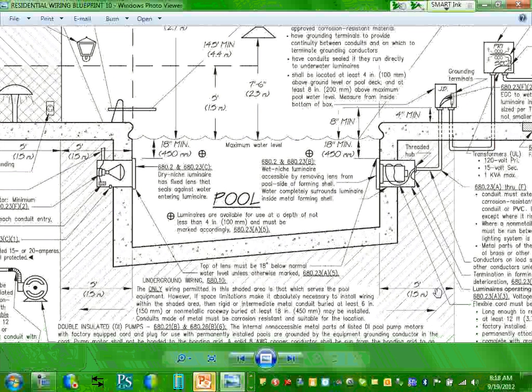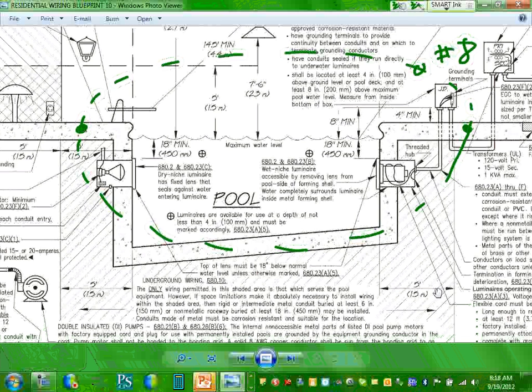All this, guys, is bonded together. What they do is they also put a number 8 conductor around the whole swimming pool. This is number 8. So as you walk the perimeter of the swimming pool, guys, I'm walking on grounded concrete, or it doesn't have to be concrete, or gravel. The ground up to 3 feet, they have a number 8 conductor around the swimming pool. Just number 8 around the whole swimming pool, within 3 feet of the inside of the swimming pool.